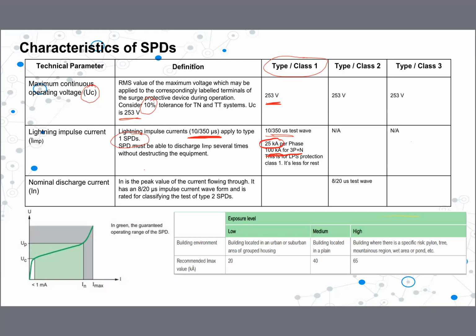We have 4 types of lightning protection classes, 1, 2, 3, 4. If it is class 1, 100 kiloampere, but if it is class 2, 3, 4, then this value is also less, right? So if your lightning protection class is 1, meaning high risk lightning protection class, then you need to use your surge protection device kiloampere level as 25 per phase, right? Then nominal discharge current, IN, right?